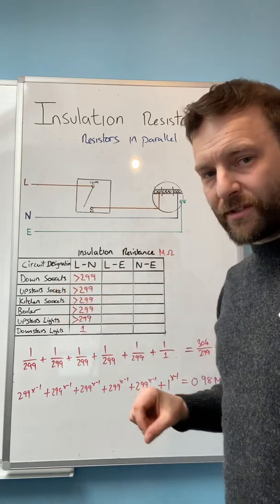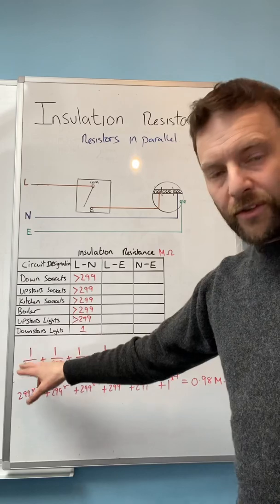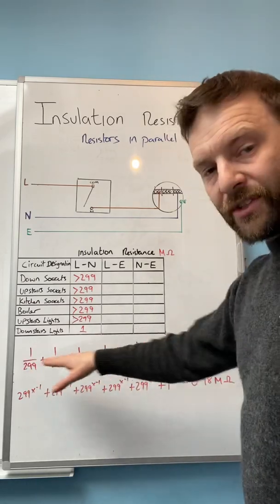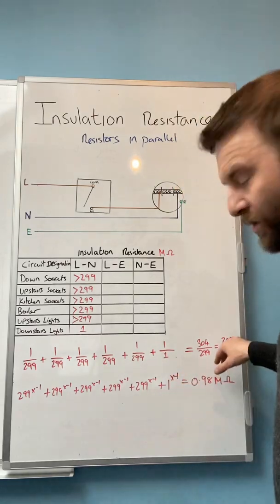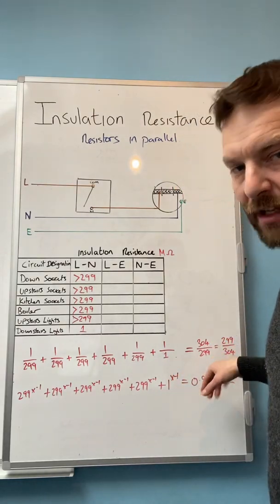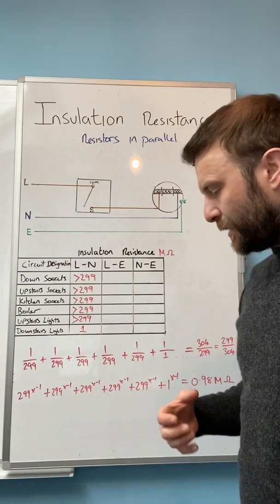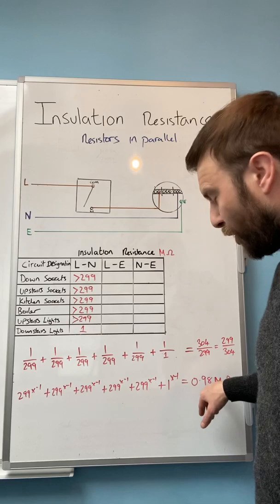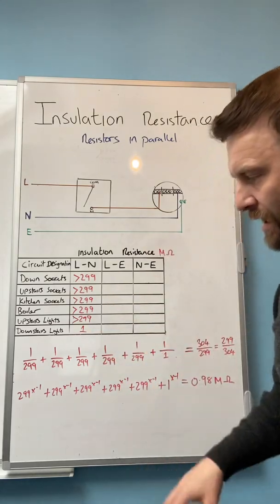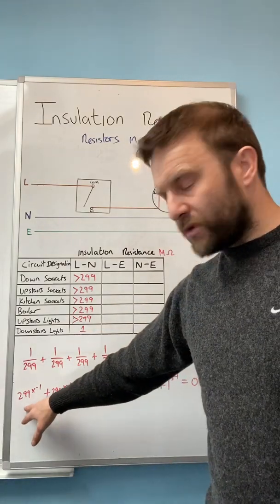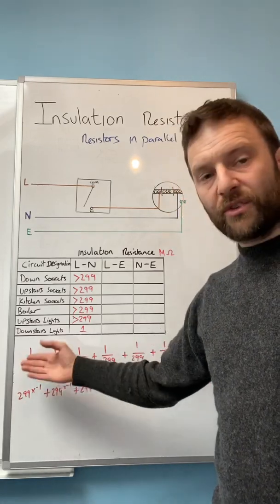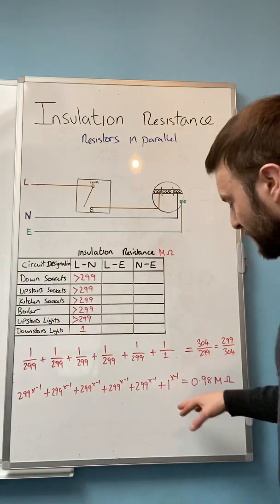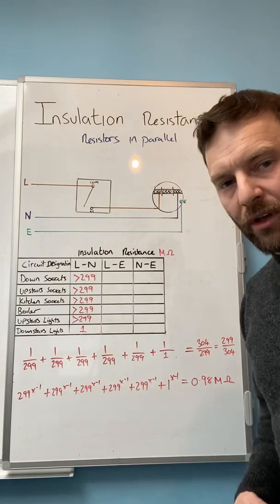How do we work out resistors in parallel? Well if you think back to college we have to do fractions. So you can either type out the fractions in your calculator and then that will give you 299 divided by 304 and then if you make that into a decimal point it will come out at 0.98 mega ohms. So we're actually below 1 mega ohm for the whole installation. If you've got a scientific calculator you could also put in 299 to the reciprocal of 1, do that five times and then plus 1 to reciprocal of 1 and that still comes out at 0.98 mega ohms.